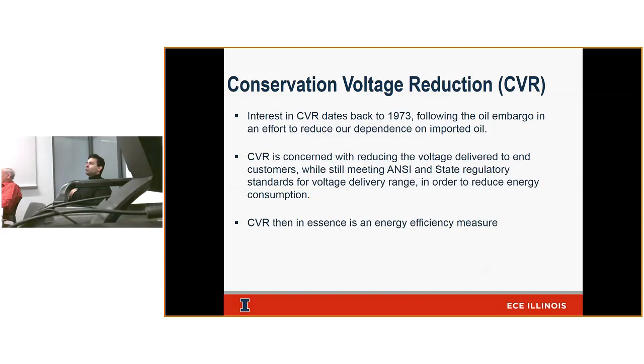If you remember from the constant impedance, constant current, and constant power types of loads, some of these would actually respond really well to reducing the voltage by overall reducing the energy consumption. So that's the theory: as you reduce the voltage on a steady state, continuous basis — not just for a short period — you should be able to see some reduction in overall energy. Unfortunately, it also reduces the revenue.